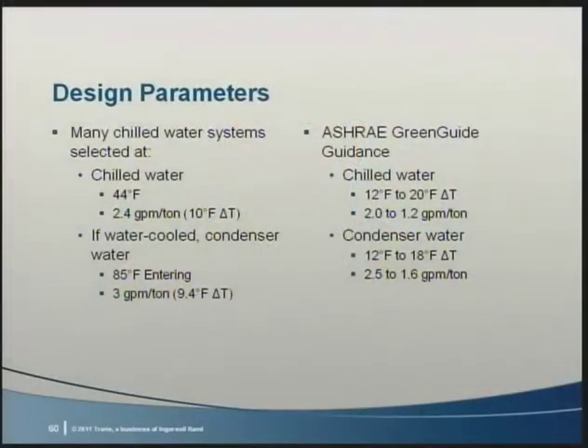In the past, many chillers were selected and systems were designed using these AHRI standard test conditions. There are a lot of chillers that were selected to make 44-degree chilled water with a 10-degree delta T, and with a condenser water flow rate of 3 gallons per minute per ton, entering at 85 degrees. In the past, this was also a 10-degree delta T, but with today's more efficient chillers, it's closer to about 9.5 degrees.